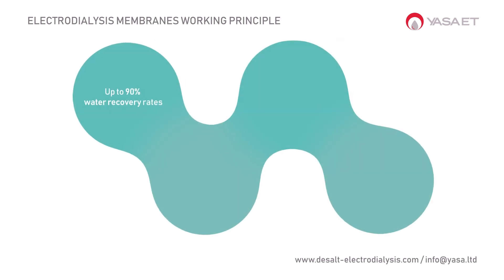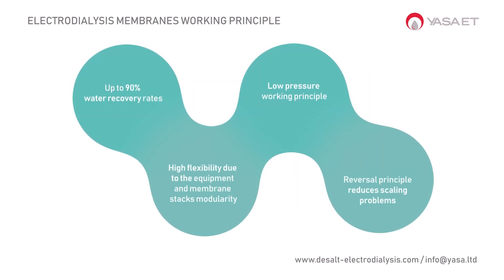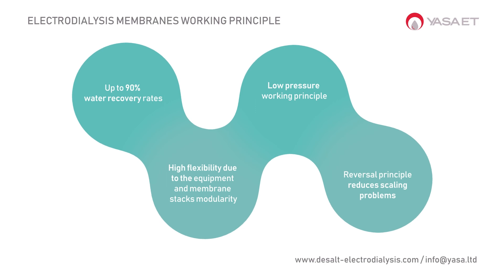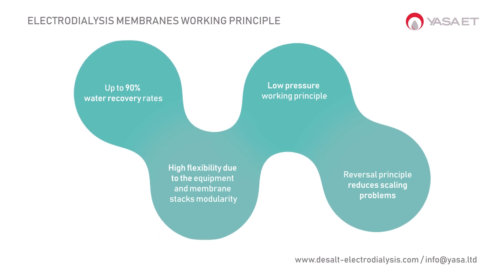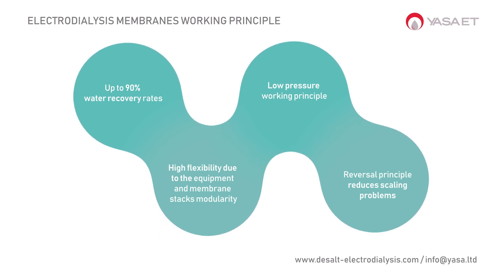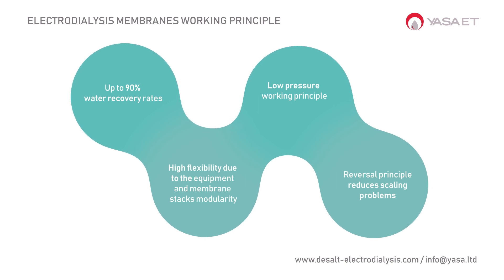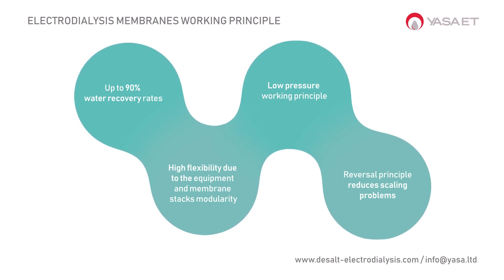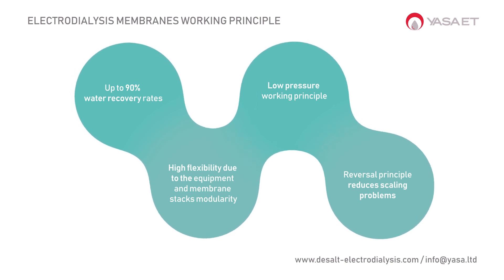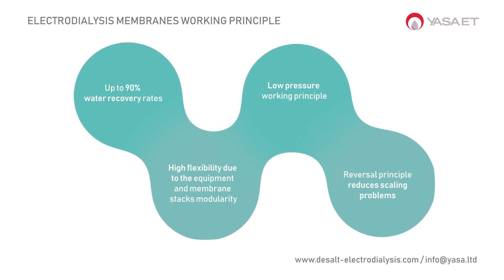Electrodialysis offers several advantages, including up to 90% recovery rates in certain applications, high flexibility due to the modular design and low pressure operation, and reduced scaling issues thanks to the reversal principle.